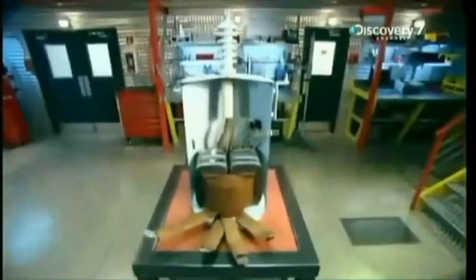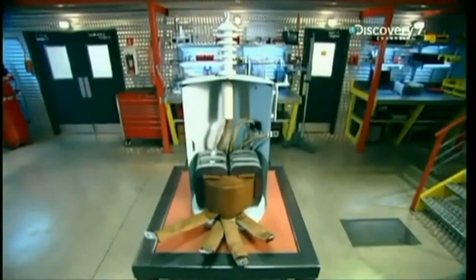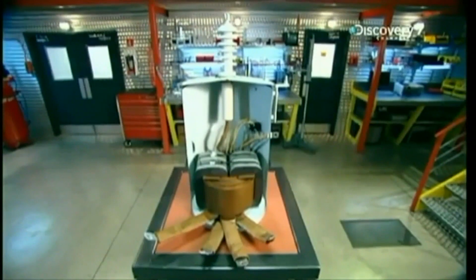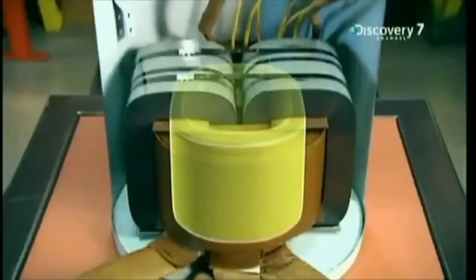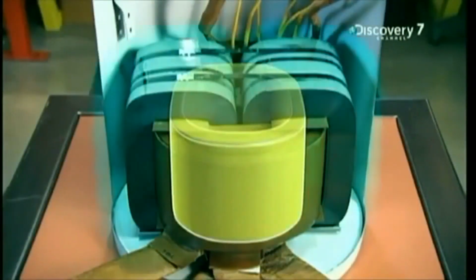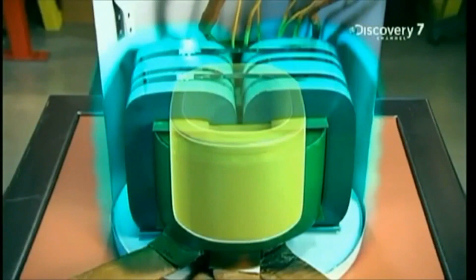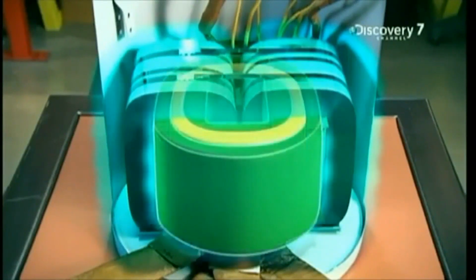Let's go over it. The metal leaves of the coils never touch. They're insulated from each other thanks to the oil-soaked paper. No short circuits to worry about. The 25,000 volt current surges through the primary coil, generating a magnetic field in the metallic core surrounding the coils. An electric current is induced in the secondary coils.